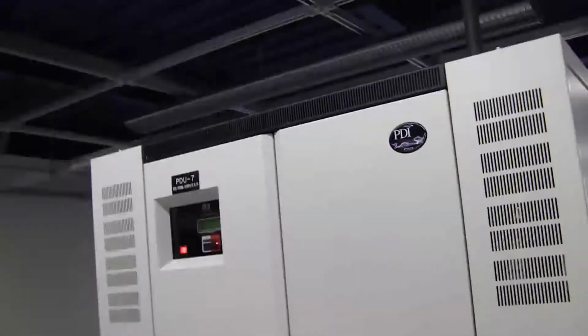The electrical source from the outside first comes in and goes to an automatic transfer switch. If utility power goes down from the city power company for some reason, the automatic transfer switch detects the loss of power and switches over to generator. These are behind a UPS. So basically it goes: utility power, automatic transfer switch, UPS - which has a power rectifier in it that cleans the power - then PDU, then customer panel.